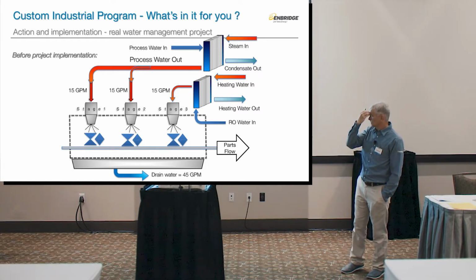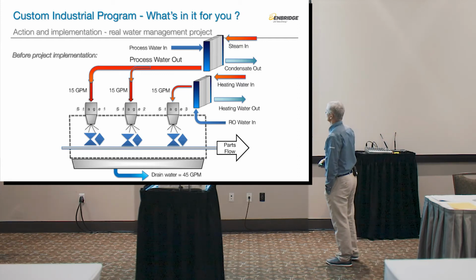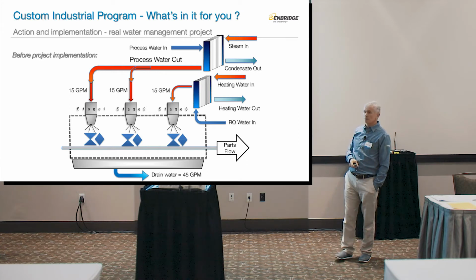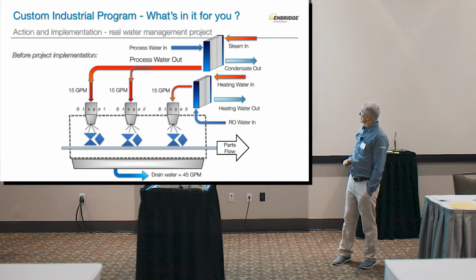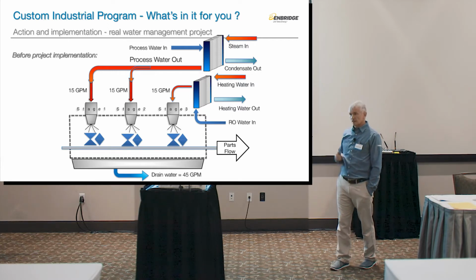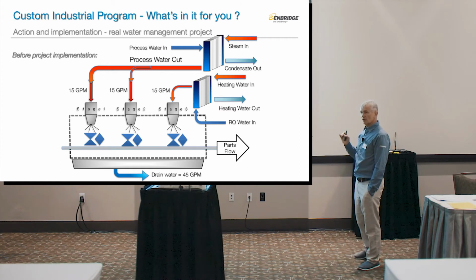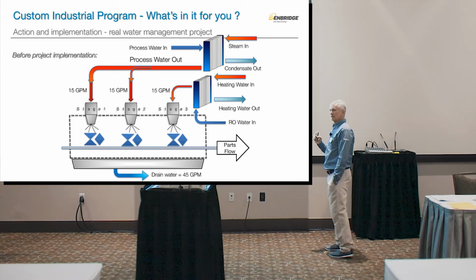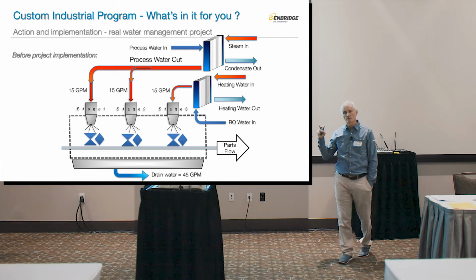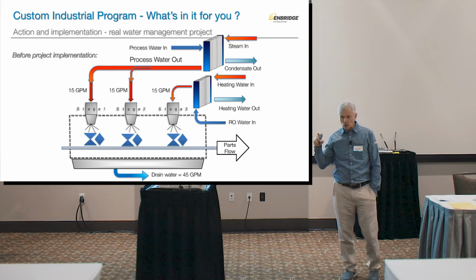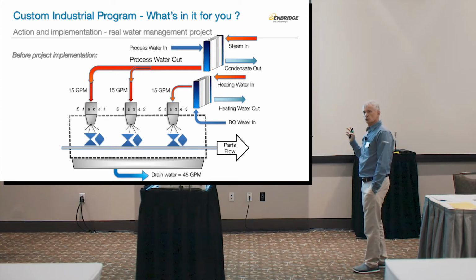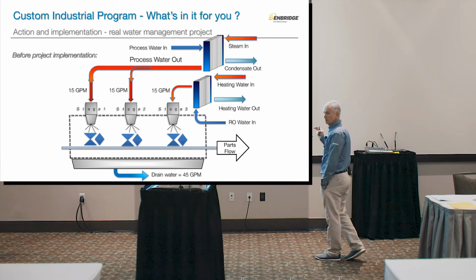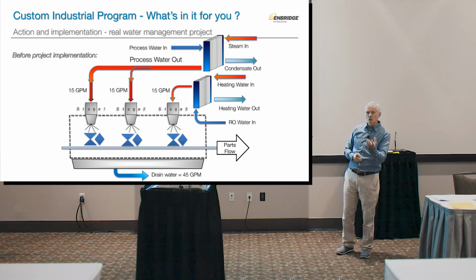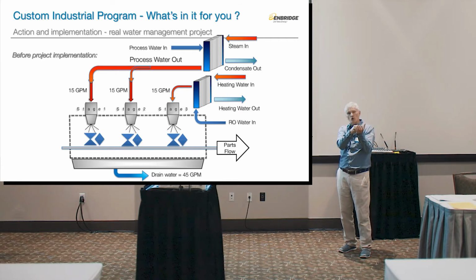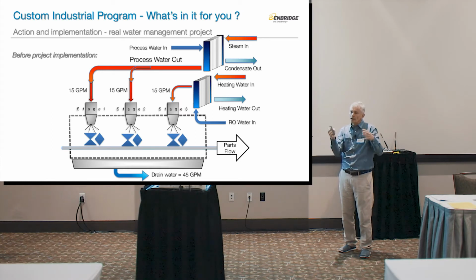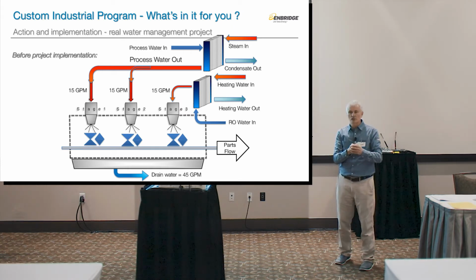In the first 2 stages, it was processed water, just regular city water, heated. That was heated by steam through the steam heat exchanger. And then for the other 15 GPM, at the last stage, which was critical for their process, they actually use RO water. So they heated RO water with the heating water that they generated in a direct contact water heater. And a direct contact water heater, for those who don't know, is the most efficient way to generate hot water. It's almost 100% efficient because you use exhaust gas to preheat the cold water by dripping it through the exhaust gas. So you get all the latent and the sensible heat out of the exhaust, and you get the most benefit.